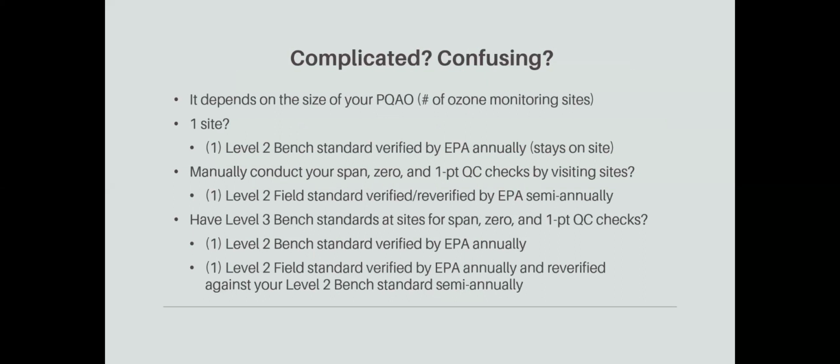So my next question, does this seem pretty complicated, confusing? It does. But you can break this thing down to something simpler by understanding the size of your organization, by the number of ozone monitoring stations you have. Quite simply, if you only have one site, which is pretty common, you only need one level 2 bench standard that EPA will verify annually, and you'd leave it at your monitoring location.